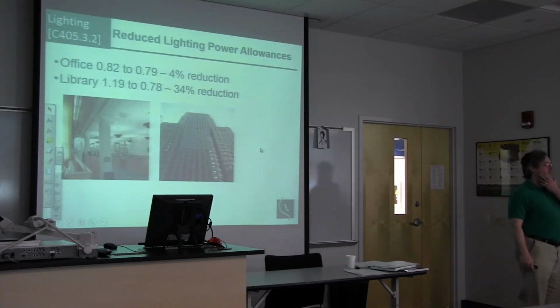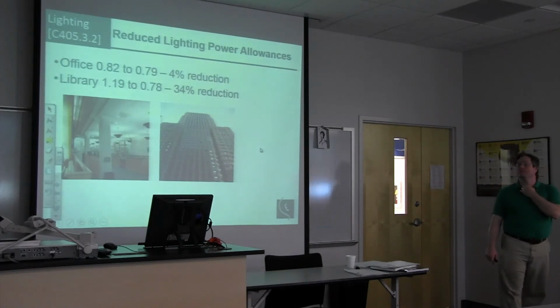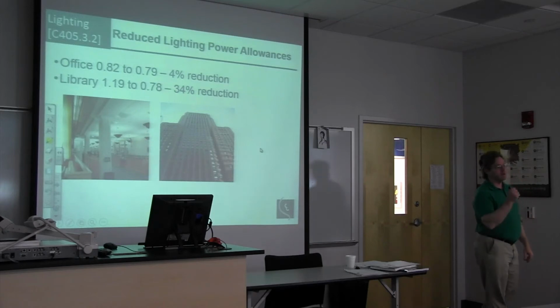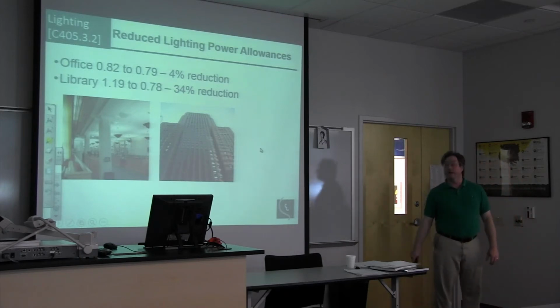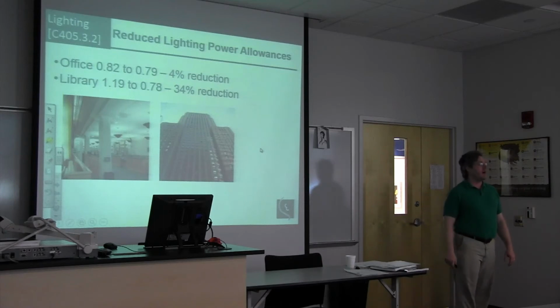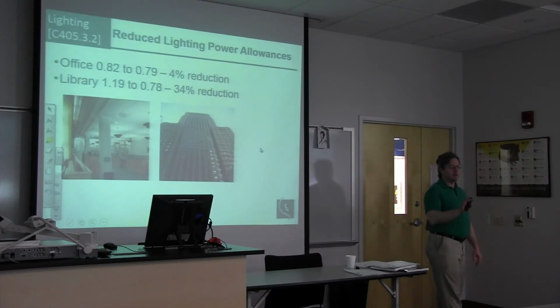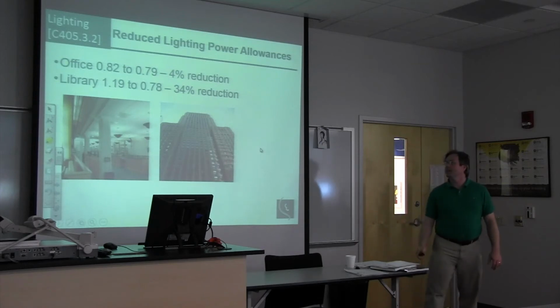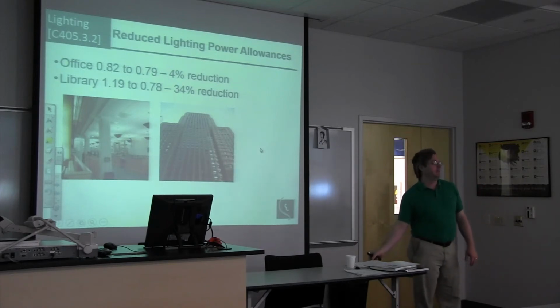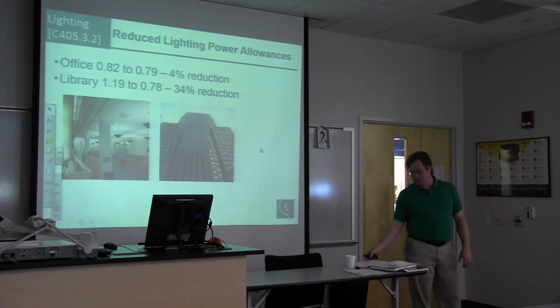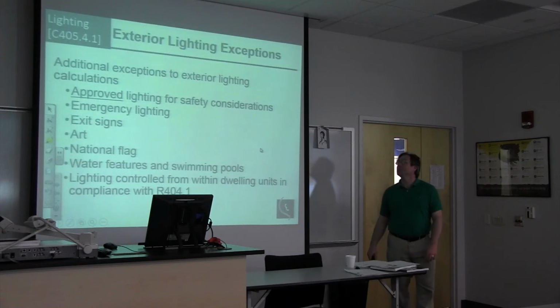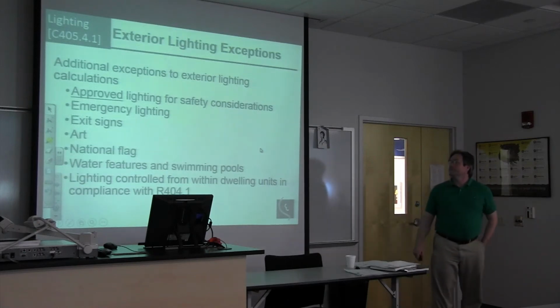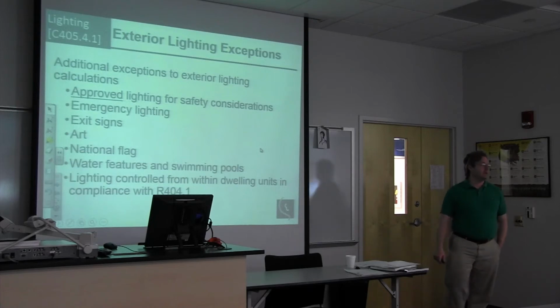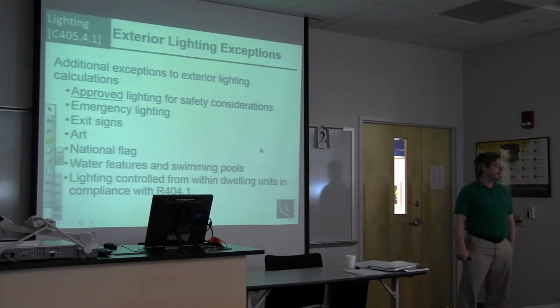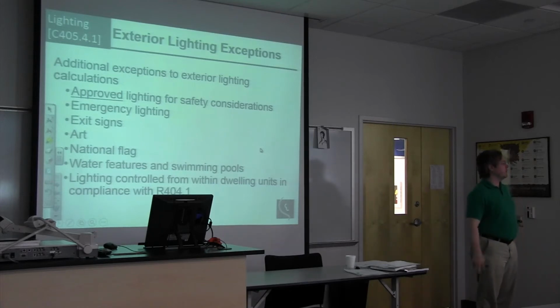Again, lighting keeps getting more efficient, so we're reducing our lighting power requirement even further now. A little bit less in offices. Libraries have taken the biggest hit in this round. They are now just below the level of office lighting, which seems a little strange to me, but it is what it is. Even at 0.78, with as good as fixtures are getting now, you can still produce a fair bit of light with that. Exterior lighting, they've now excluded more exterior lighting from the calculations as far as what your lighting power for exterior is.